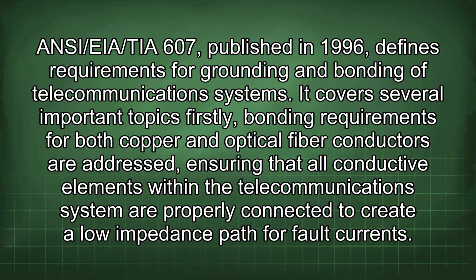ANSI/EIA/TIA 607, published in 1996, defines requirements for grounding and bonding of telecommunications systems. It covers several important topics. Firstly, bonding requirements for both copper and optical fiber conductors are addressed, ensuring that all conductive elements within the telecommunications system are properly connected to create a low impedance path for fault currents.